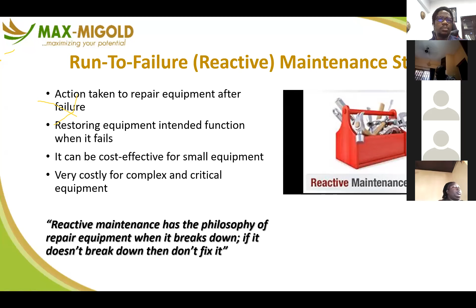If you have provided 3 systems that operate one at a time and cover the capacity of that asset, why do I want to use another strategy to maintain those assets? I'll use run to failure, even if they are critical assets, air conditioners for example. Why? If one of the air conditioners develops a fault, starts making noise, starts dripping water, starts warming up, I simply switch to the next and send the one presenting a fault out for repair.